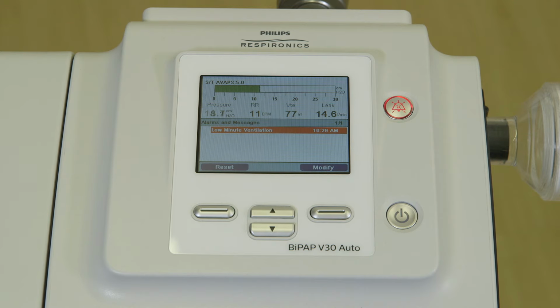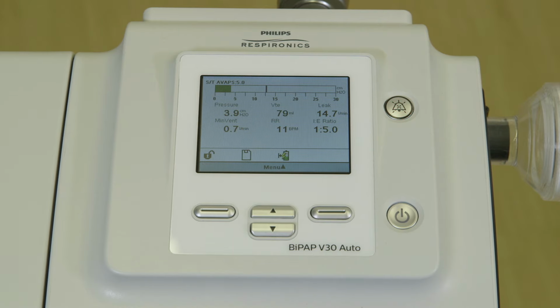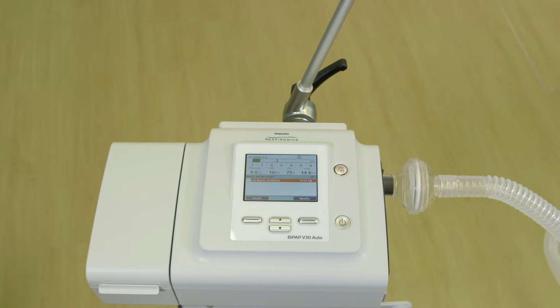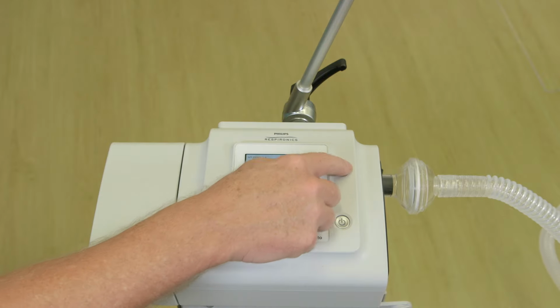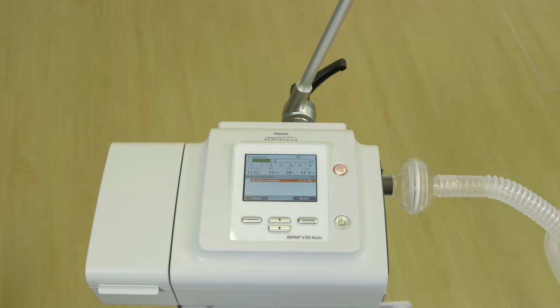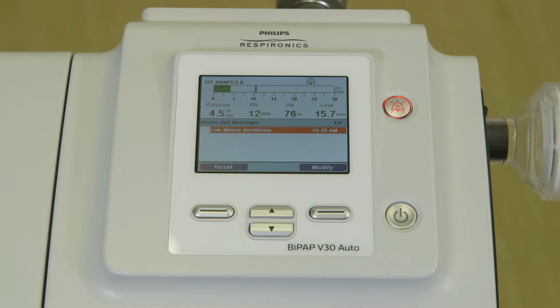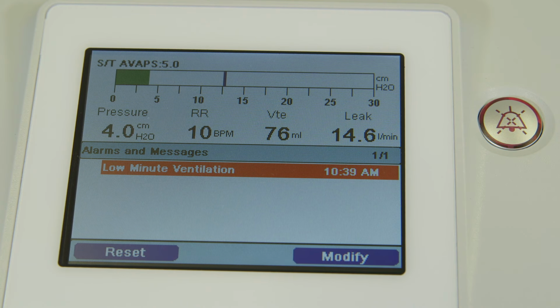The V30 Auto has a full complement of patient and system alarms, as well as information messages. In the case of each of these high-priority alarms, the V30 will continue to operate, and the audible sound will terminate once the alarm is resolved. When an alarm is active, the clinician can silence the alarm for 60 seconds by pressing the alarm indicator and audio pause button. If the cause of the alarm is not corrected during that time, it will continue to sound until corrected, or until there is an additional press of the alarm indicator and audio pause button to add 60 seconds. You should note that there is also a pre-silence alarm feature. If an alarm occurs during that time, the audible indicator will not sound until the end of the silence period. Refer to the user manual for additional information regarding the system alarms and information messages for the V30 Auto.